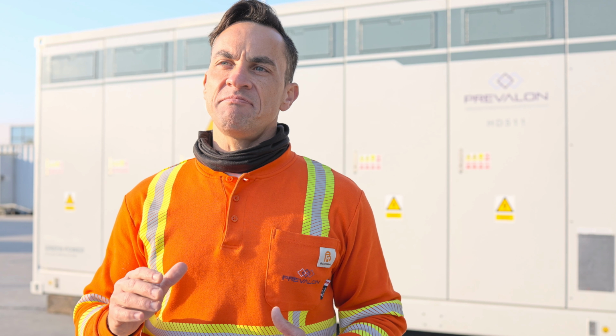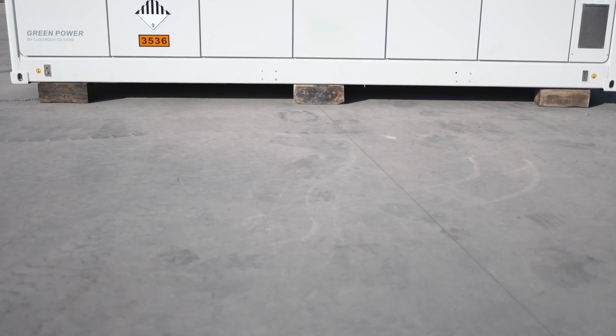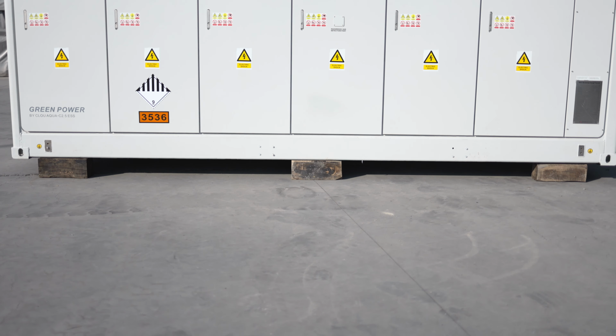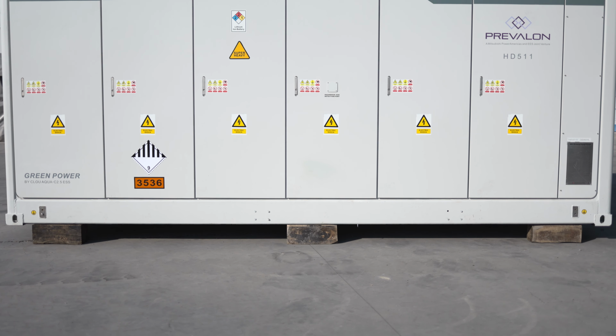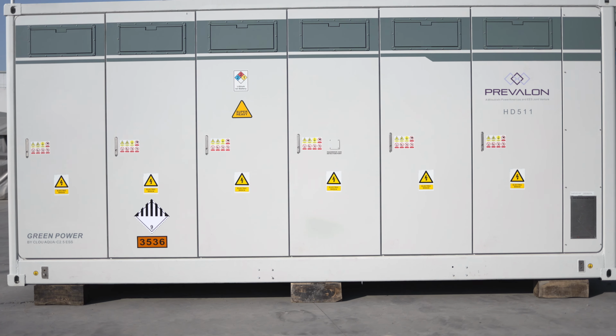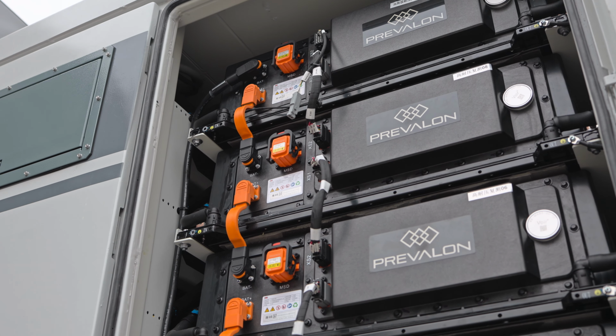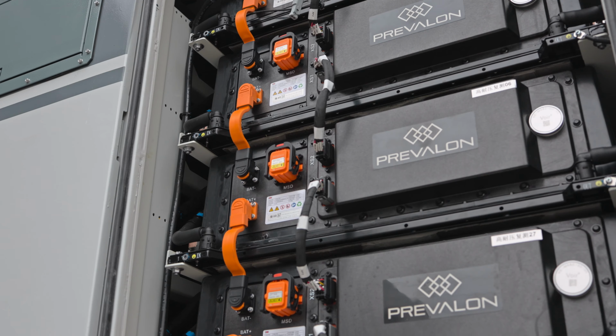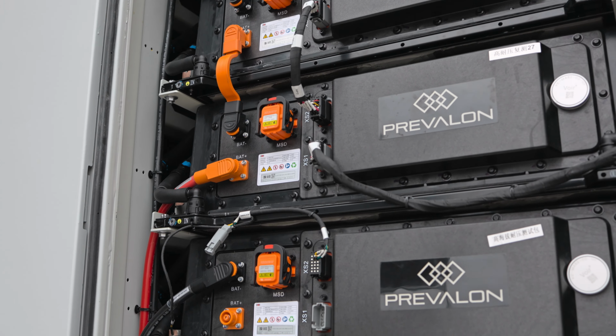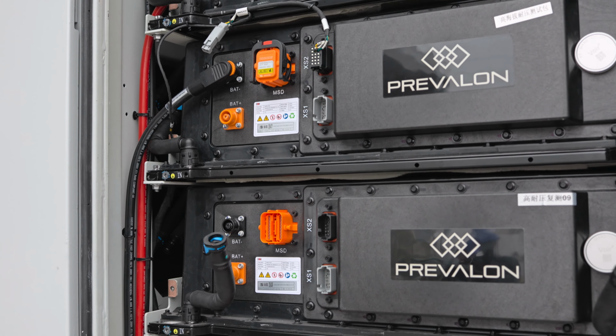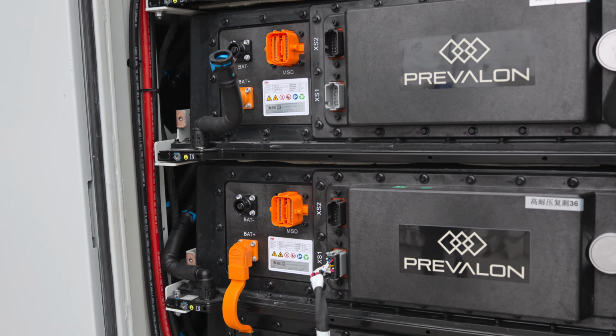The HD5 is a 5 megawatt hour LFP battery enclosure. It comes in a 20-foot ISO intermodal form factor to facilitate logistics. It weighs 44 tons and delivers to site fully assembled and ready for commissioning. It supports both bottom and side cable entry for below or above ground wiring respectively.